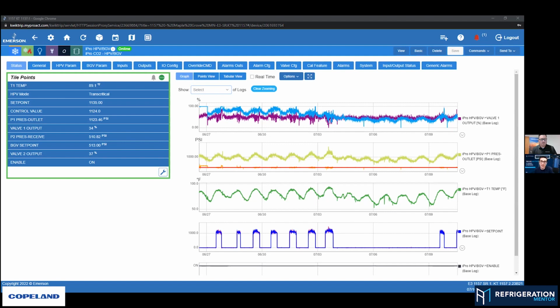I bet OEMs are loving that compared to all the other part numbers. Oh yeah, for sure. We also can expand the evaporators, so if you've got a case with more than one evaporator, we have an evaporator expansion module that plugs into the case controller, so you don't need to wire anything between it. It's like a snap block expansion module with a male end on the main controller and a female end on the other side, so they just click together. Now you've added an extra coil to that controller. So for a 12-foot case with 3 coils, you'd have a case controller with 2 expansion modules, instead of having to buy 3 different case controllers for that one case.